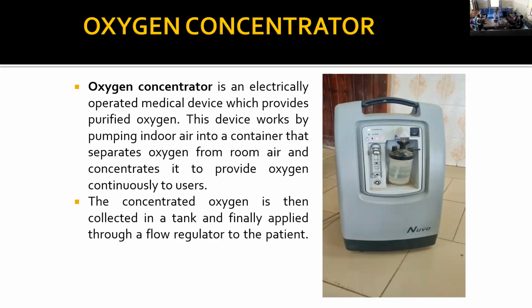Thank you. An oxygen concentrator is an electrically operated medical device which provides purified oxygen. This device works by pumping indoor air into a container that separates oxygen from room air and concentrates it to provide oxygen continuously to users. The concentrated oxygen is then collected in a tank and finally applied through a flow regulator to the patient. To another slide.